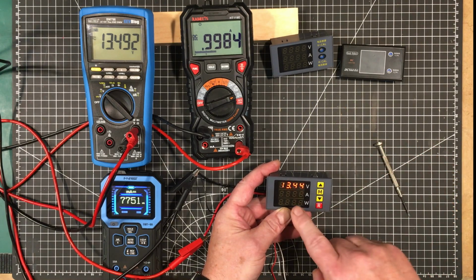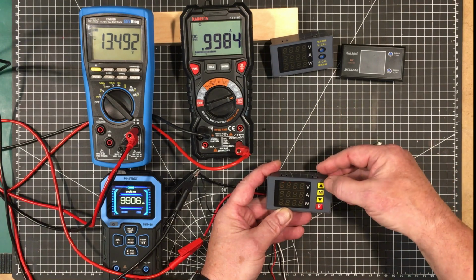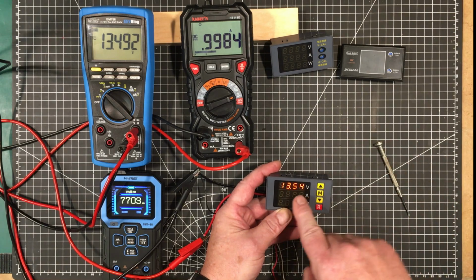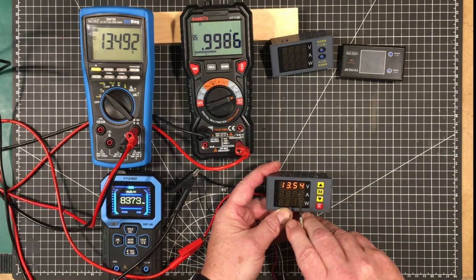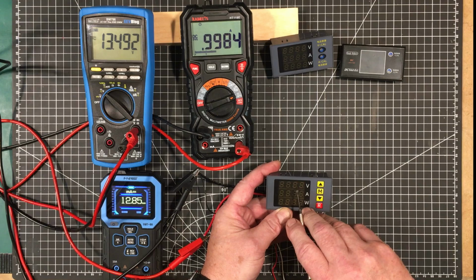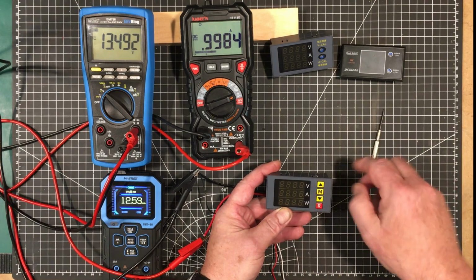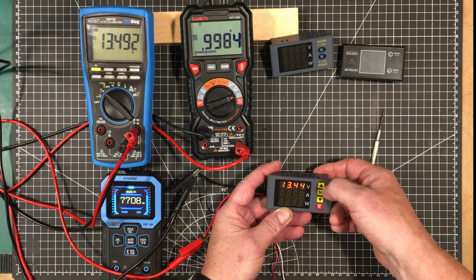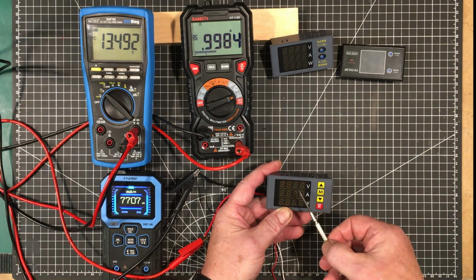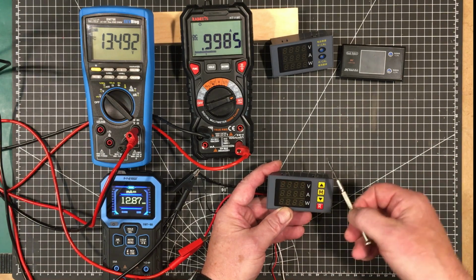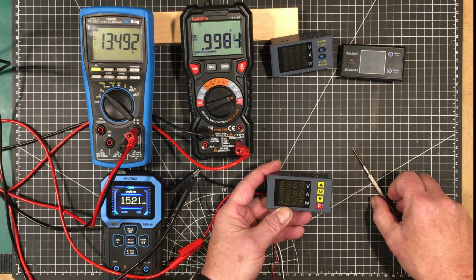And then it goes into this mode here. Now once you're in this mode, this is where you can adjust the calibration, but the calibration only adjusts on this digit here, not on this one, so it's a very rough calibration. If I was to look at this, this is actually a little bit more precise, more accurate, so I'm going to leave it there.